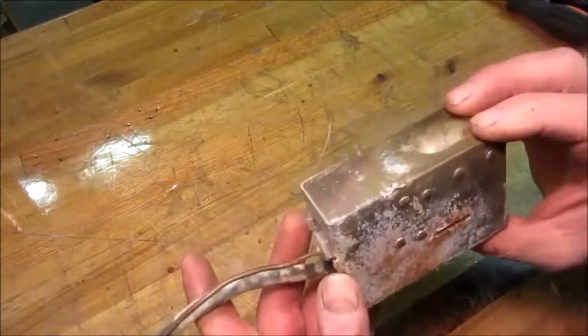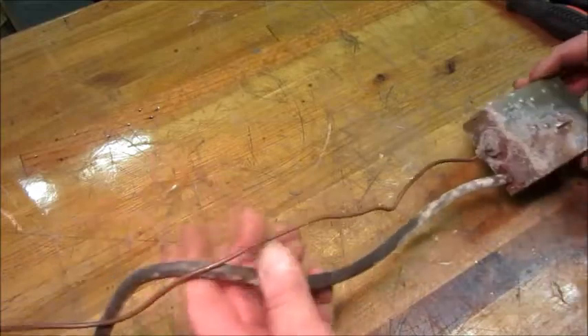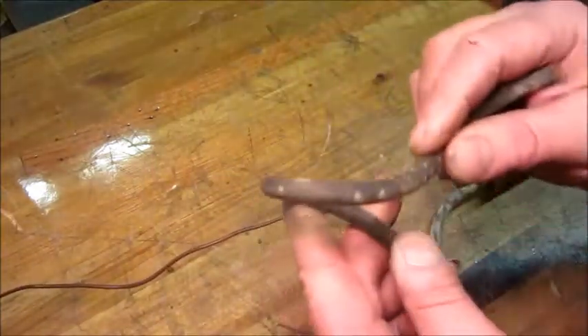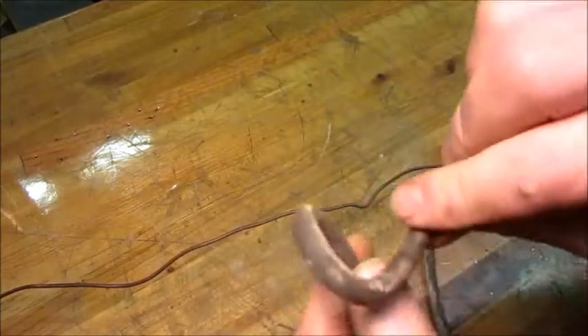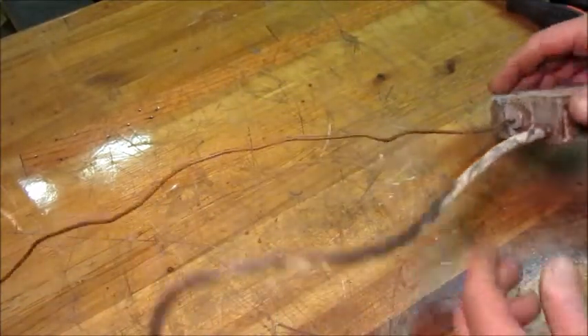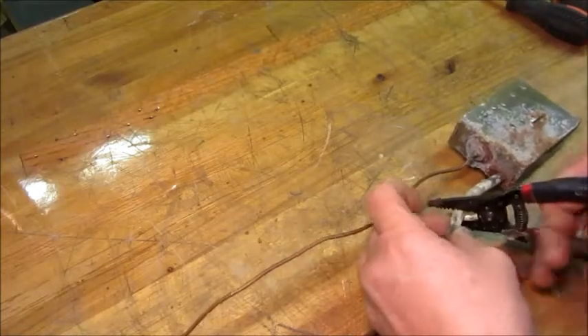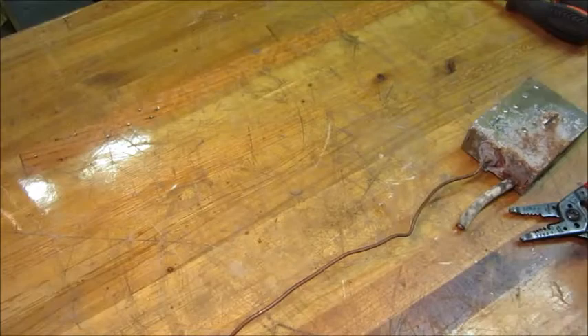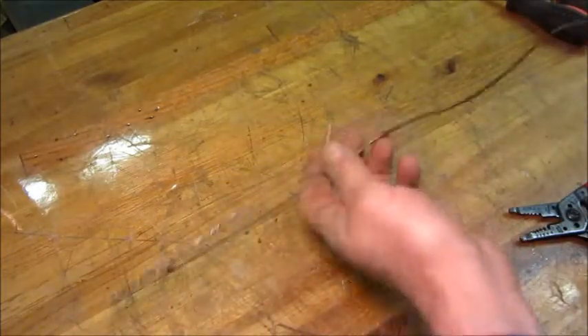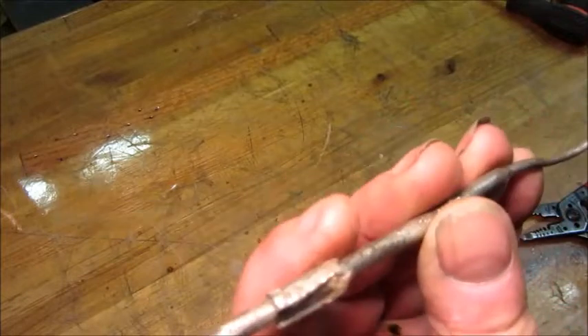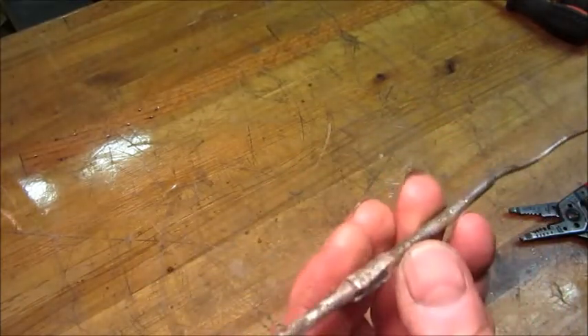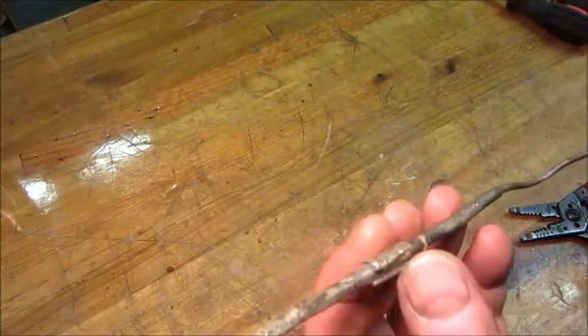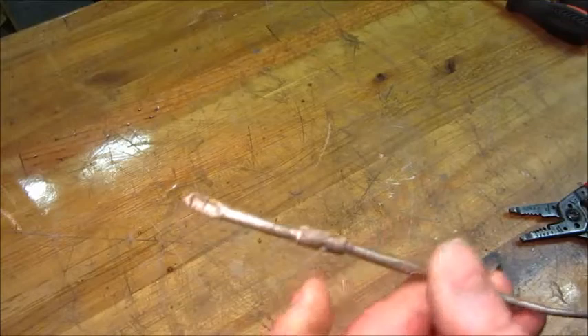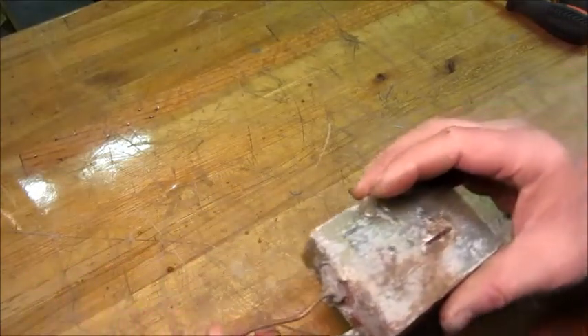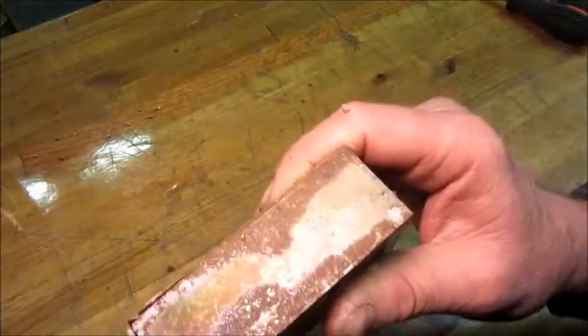So I got this Westinghouse control out of the cabinet, and the power cable, the internal wiring in the cabinet where it was protected, you know, is still very flexible, but of course it's getting replaced. To make this easier to handle, I'm going to just cut it off, get rid of it, bend it. One thing I did have to do, they had soldered a bracket onto the sensing bulb here. The only way I could get that off out of the cabinet was to cut off the bracket. So I'll put a different bracket that's clamped on for reassembly, but that tells me this is the original thermostat. It's probably never been out before. One thing I noticed, what do you not hear?